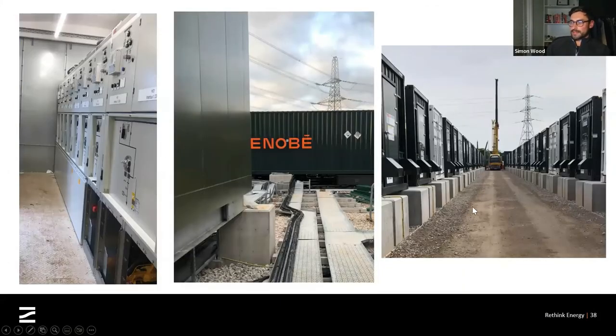Some more general pictures across the site. This is inside one of the MV control rooms. So this is the switchgear. This is essentially all 33 kV circuit breakers here. So all of our points of isolation, protection systems and control mechanisms. And that's housed basically inside that modular building that I showed on the previous slide.